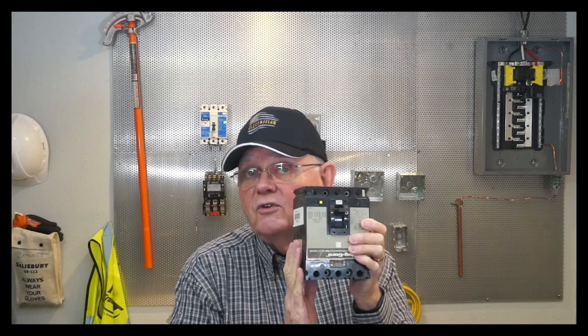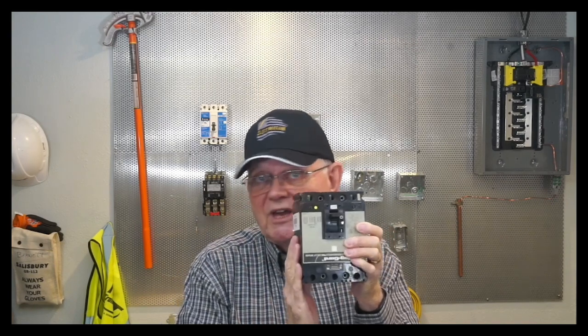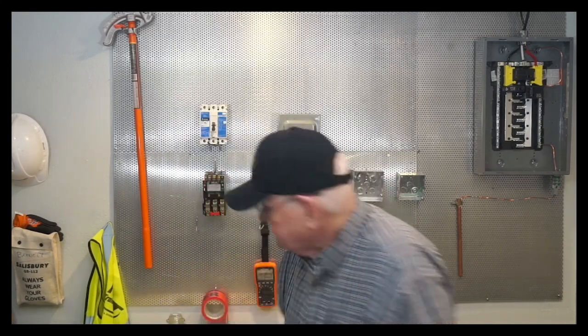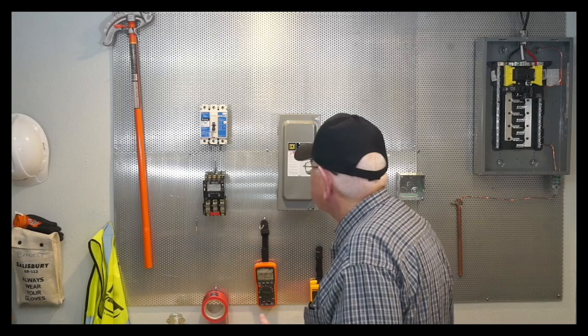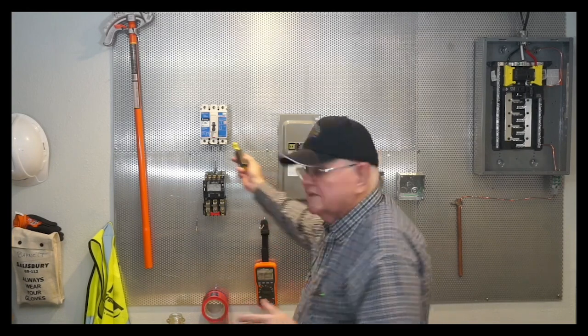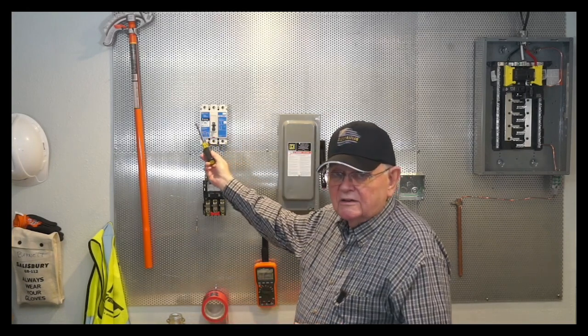And all it sets is the pickup value. It does not set any time delay. No intentional time delay, but I can set the pickup values on this particular breaker. Often referred to as motor circuit protectors. Let's take a look at an example back behind me. This is an instantaneous trip circuit breaker, so we might call it a motor circuit protector.